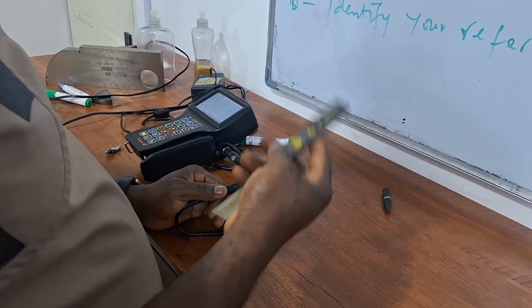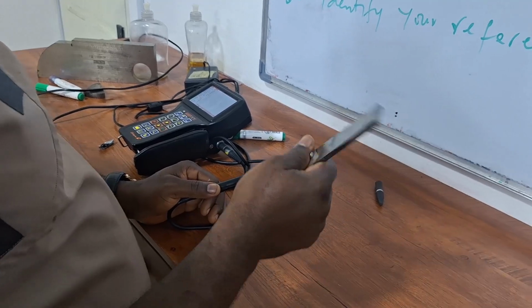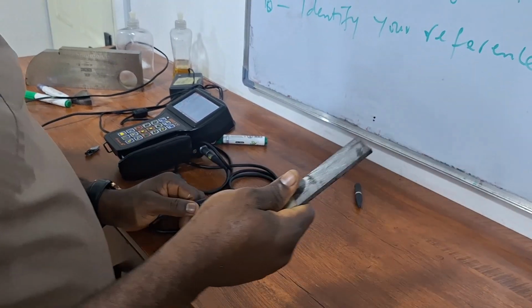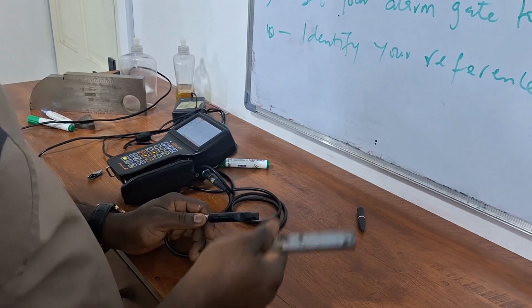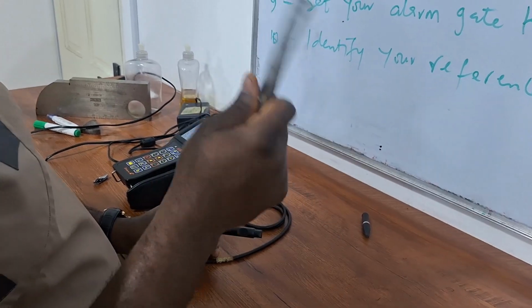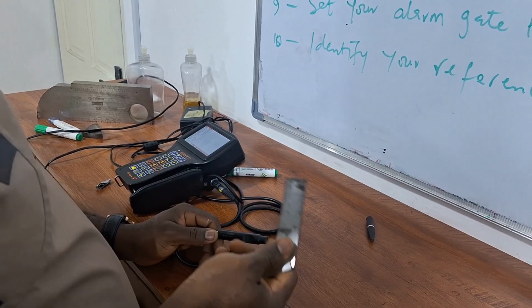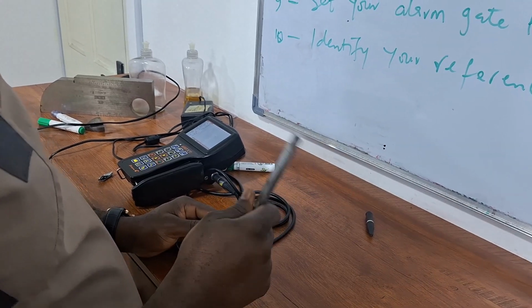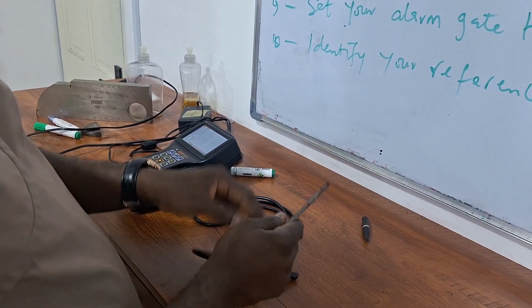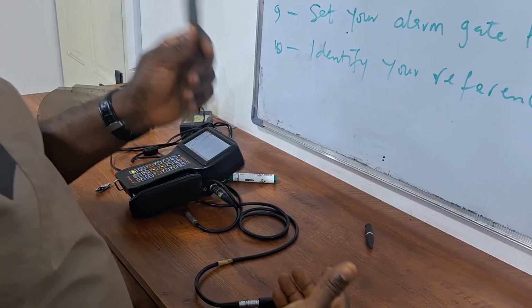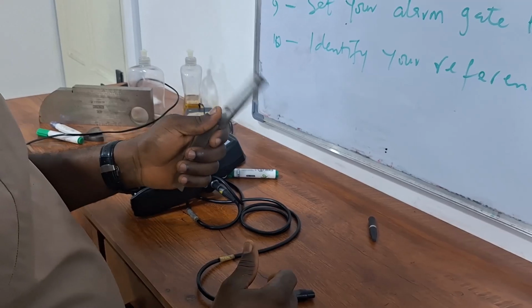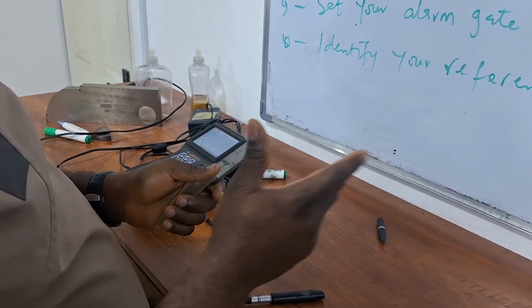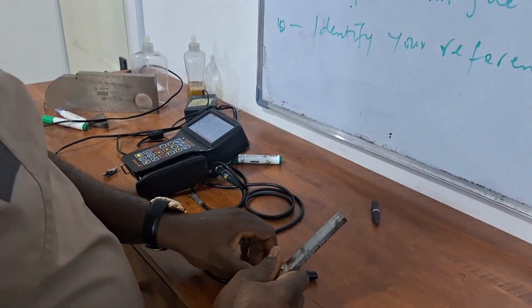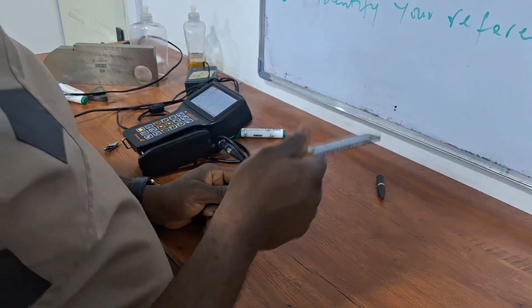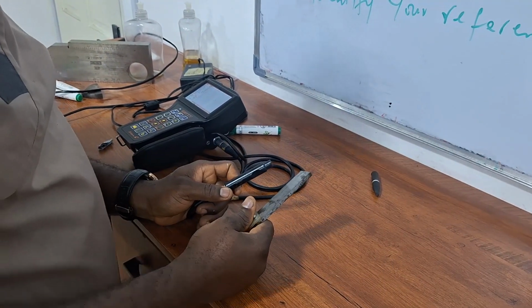Then the next thing you need to have is the right calibration standard, which is key, because if we are working with stainless steel and we use carbon steel to calibrate for stainless steel, it's going to give us an issue. For example, we know that carbon steel is magnetic and stainless steel is not magnetic, so it's going to affect the impedance value, because one is ferromagnetic, one is not. So you need to take note of that. So choose the right calibration block, the right calibration standard.